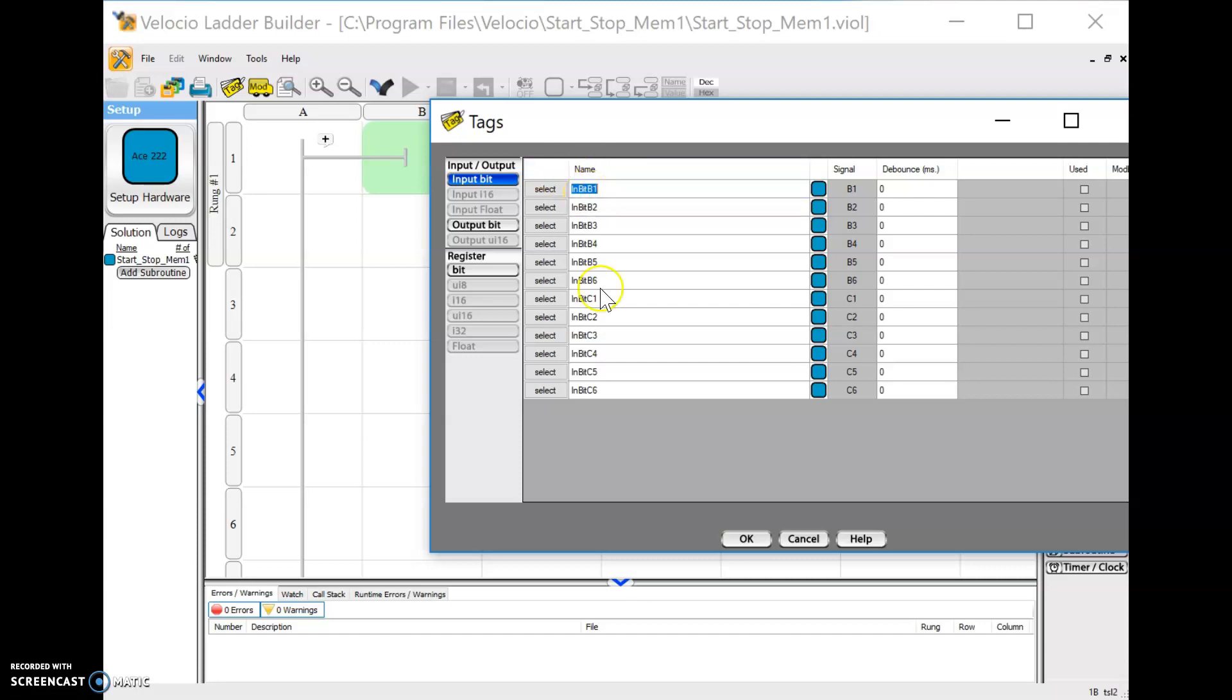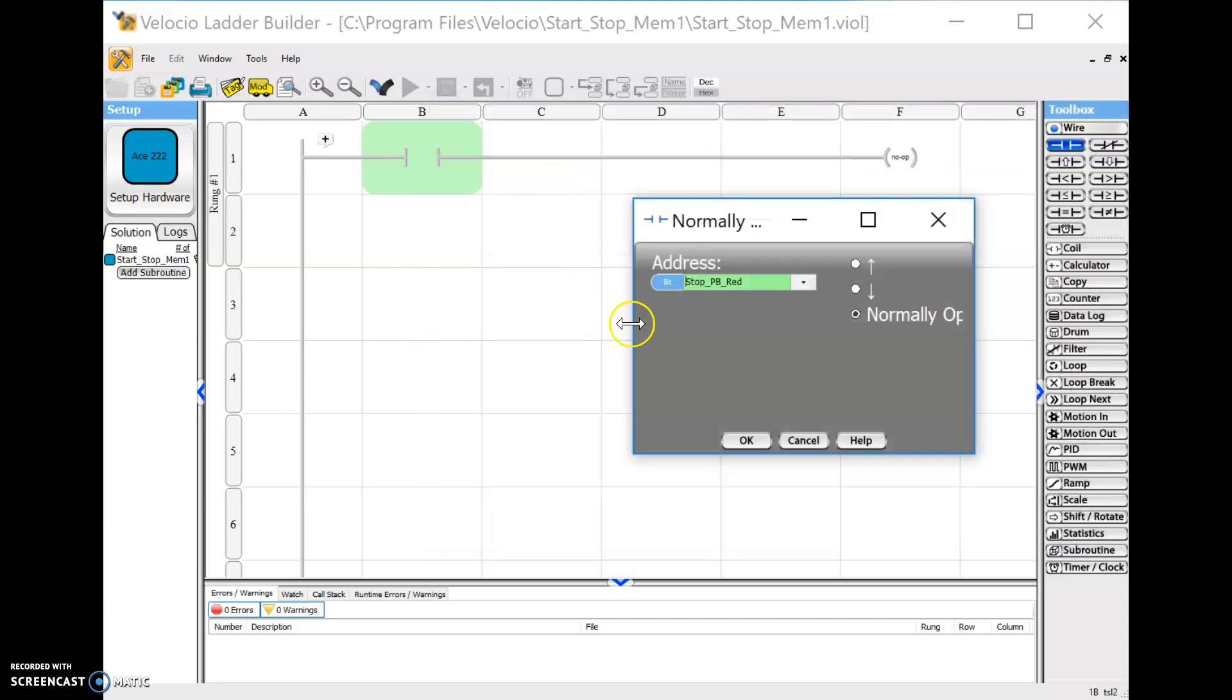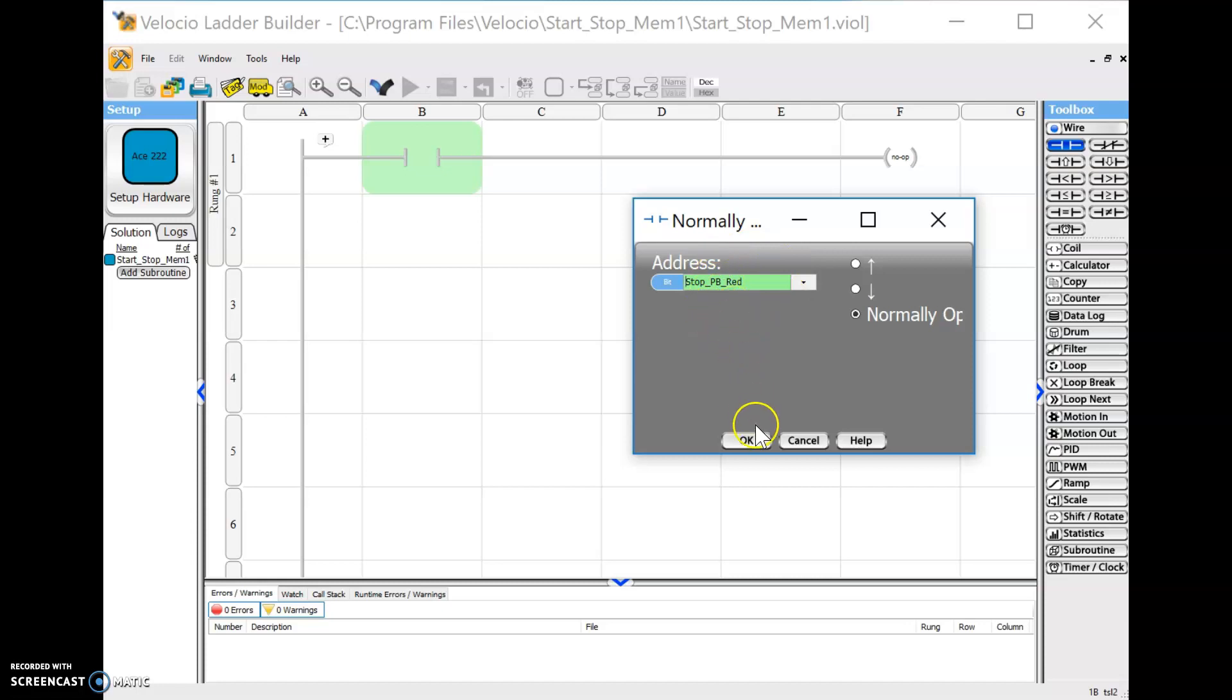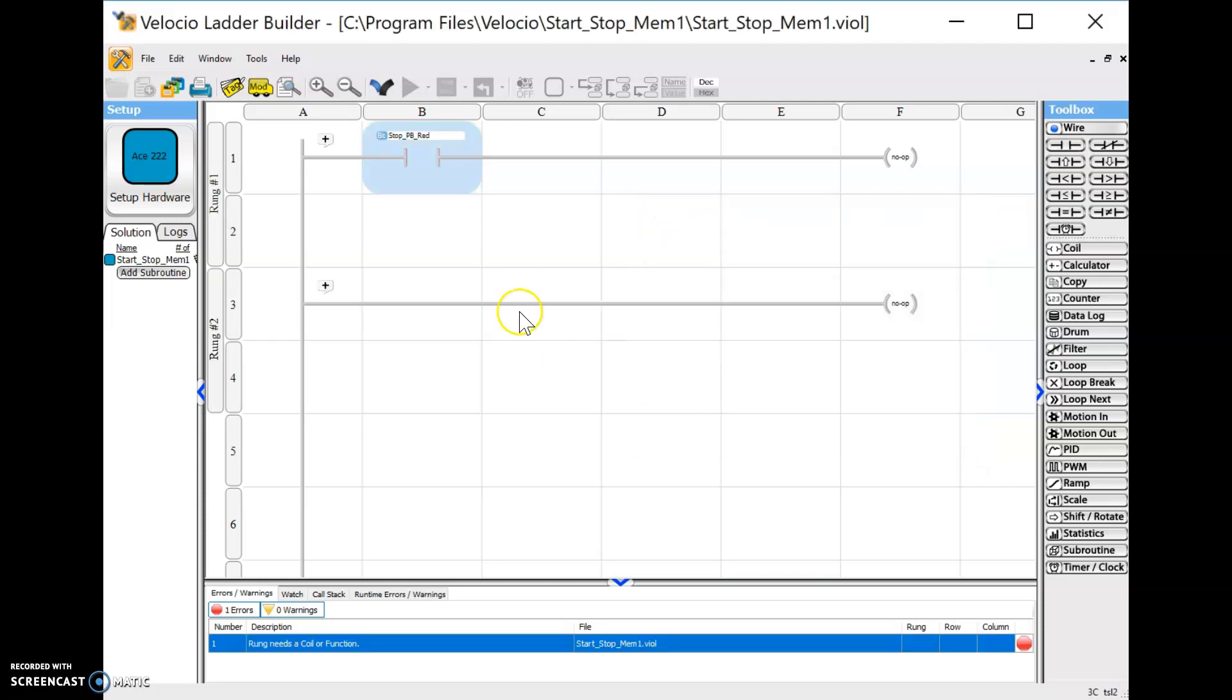This one we're looking at is going to be an input bit, which is a digital in. So on this particular type of PLC, it's got banks of inputs. The first bank is B1 and the first input, you know, B1. So we're going to click it again to select it and we're going to rename it. So usually on your ladder diagrams, you always put the stop push button first. And they don't like spaces, so we got to put underscores in there. PB stands for push button. And for the stop, we're going to go with red. Put the color in there, nice little instruction, right? Now if you did it right, it does populate here and a green little background shows. Hey, it's done right. Yay, hurray for my team. So we're going to okay that and it sends that address, the tag, there.